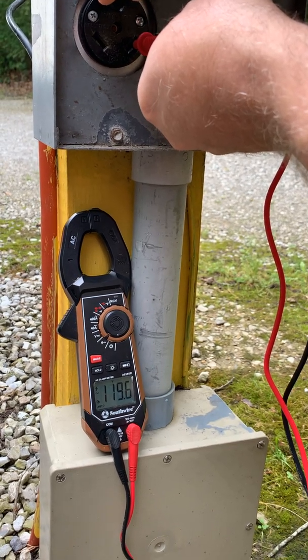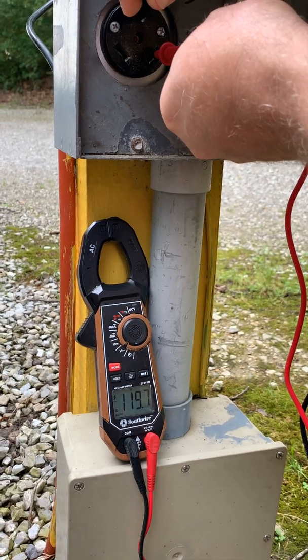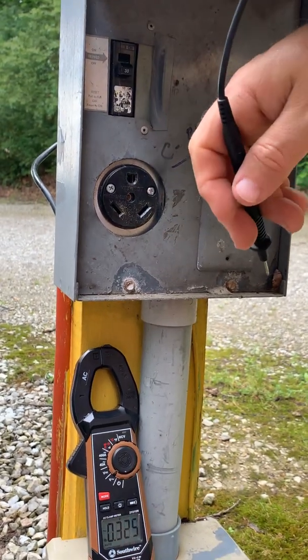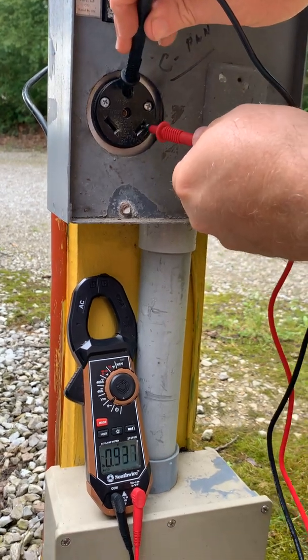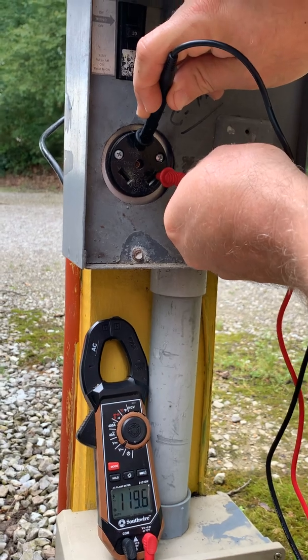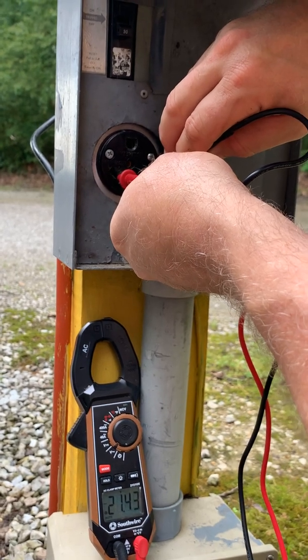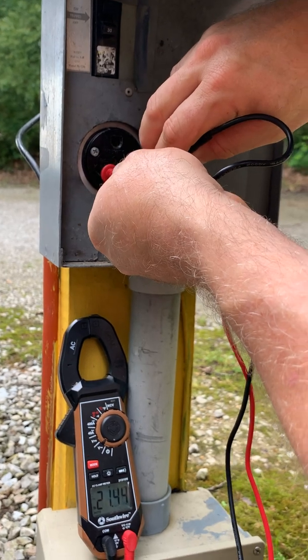But here's what's even worse. I'm going to turn the circuit breaker off — no power to anything, right? Let's go back: neutral to ground, still 120 volts. Hot wire — nothing, which is good. Actually, the hot wire is still throwing out 120 volts. So this is a bad situation. This is called reverse polarity, and it's something you need to check.